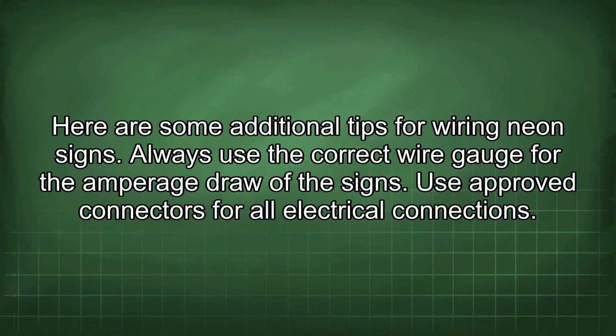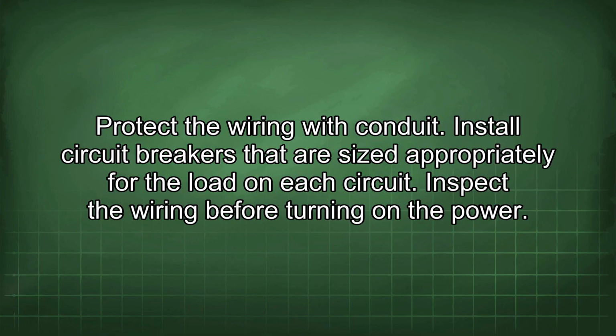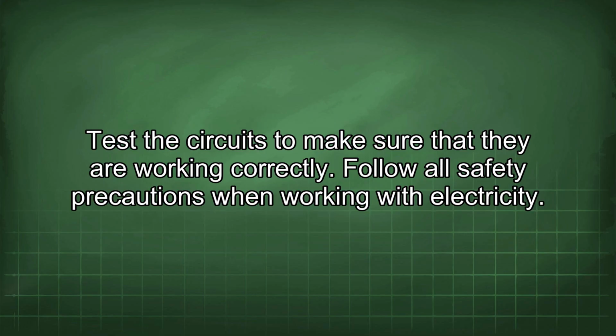Here are some additional tips for wiring neon signs. Always use the correct wire gauge for the amperage draw of the signs. Use approved connectors for all electrical connections. Protect the wiring with conduit. Install circuit breakers that are sized appropriately for the load on each circuit. Inspect the wiring before turning on the power. Test the circuits to make sure that they are working correctly. Follow all safety precautions when working with electricity.